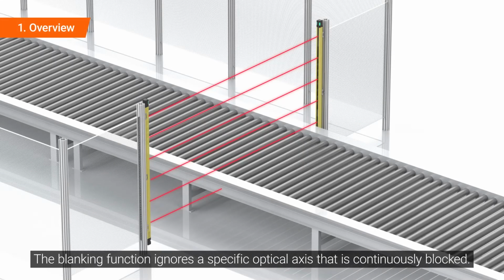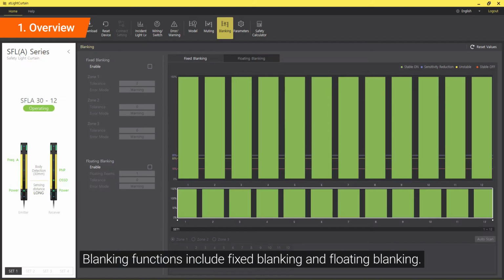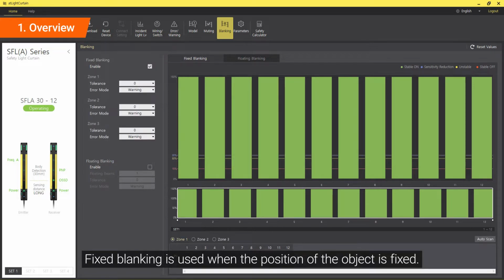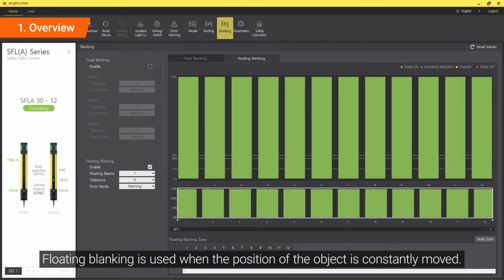The blanking function ignores a specific optical axis that is continuously blocked. Blanking functions include fixed blanking and floating blanking. Fixed blanking is used when the position of the object is fixed. Floating blanking is used when the position of the object is constantly moved.